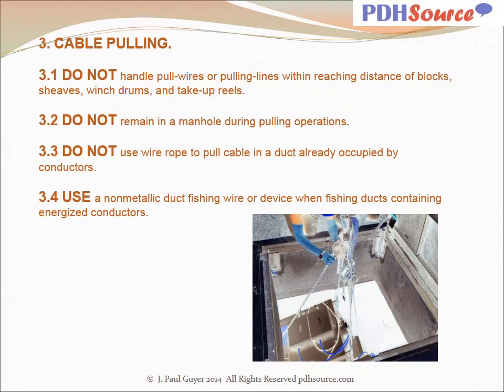Do not handle pull wires or pulling lines within reach of blocks, sheaves, winch drums, and take-up reels. Do not remain in a manhole during pulling operations. Do not use wire rope to pull cable in a duct already occupied by conductors. Use a non-metallic duct fishing wire or device when fishing ducts containing energized conductors.